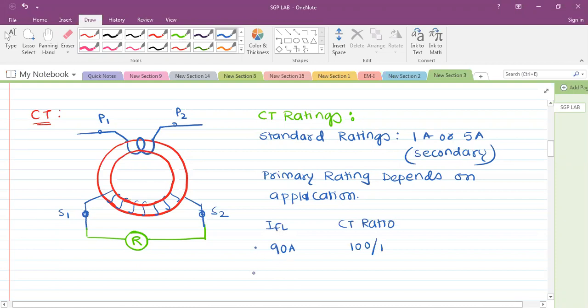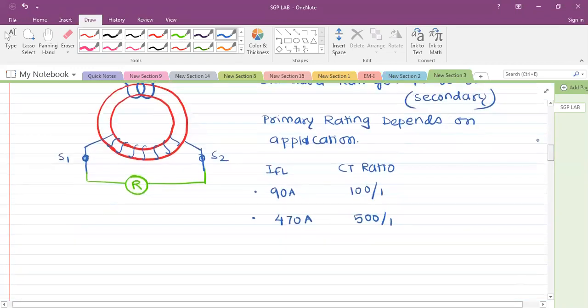Another example: a transformer has a primary rating of, say, 470 ampere. What will you do? You will select a CT ratio of 500 bar 1. For a generator where the current is say 850 ampere, you will select a CT of 1000 bar 1.